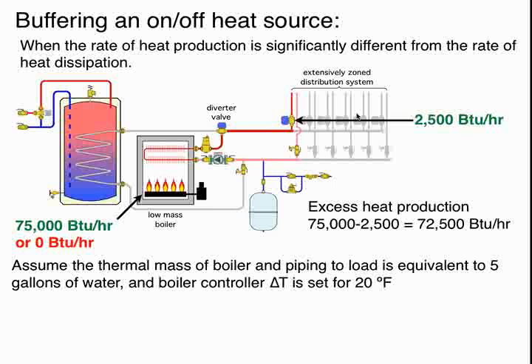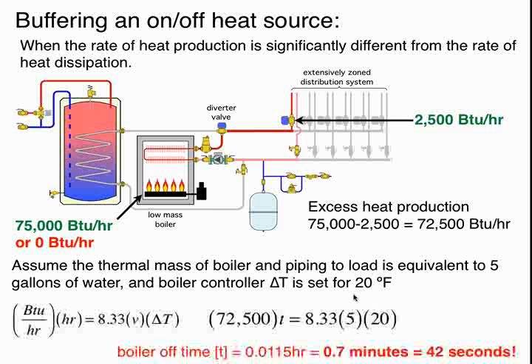All right? Now let's assume that the water that's in this low mass boiler and the metal content, as well as the water that's in this one zone distribution system. In other words, if you look at this path here that I'm tracing out with the cursor, let's assume that's equivalent to 5 gallons of water. It has the thermal mass equivalent of 5 gallons of water. And let's assume that the controller on the boiler is set for a 20-degree temperature differential. So it has some set point. I'll pick a number. Let's say it's 170 degrees Fahrenheit. When it drops down to 20 degrees below that set point, the burner goes on again, a 20-degree swing.